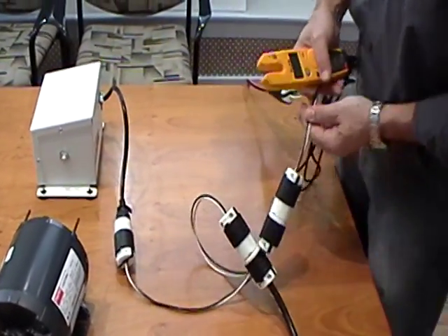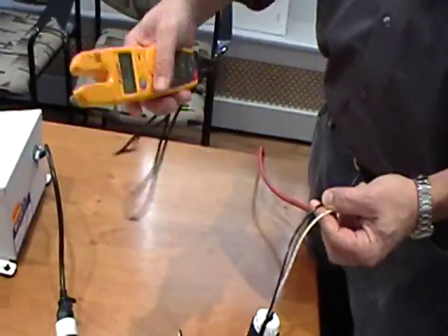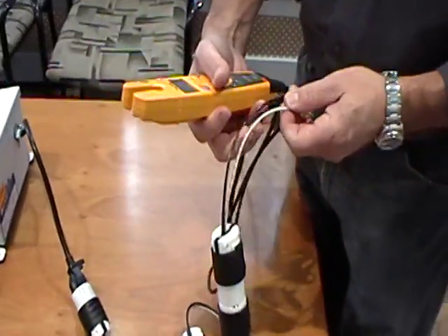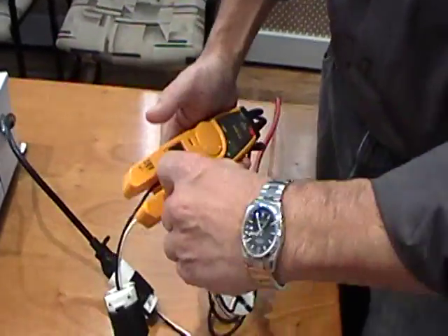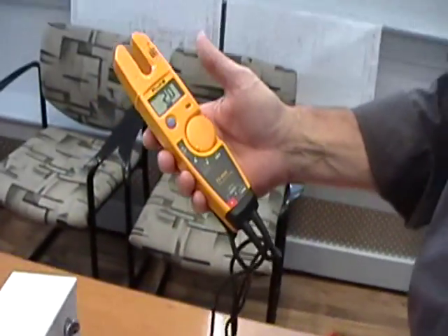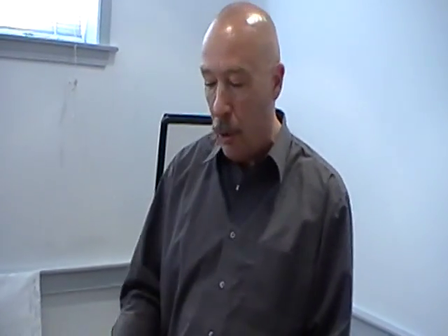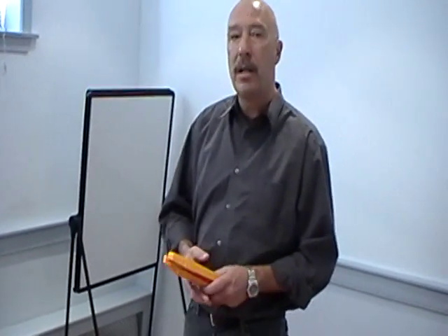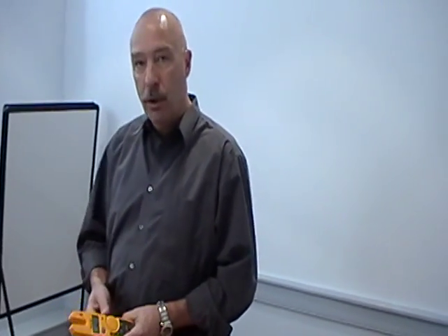Now we're going to check the power on the distribution system. In theory, we should have eliminated all that wasted current off the distribution system from this point back. 2 amps. We've taken 60% of the wasted current off the distribution system, trapped it at the motor load. This greatly reduces the strain on the distribution system. Probably 30% of the applications we deal with are industrial facilities who think they need a new service entrance because their distribution system is maxed out. This is pretty good proof that we can eliminate that problem just by installing capacitors.